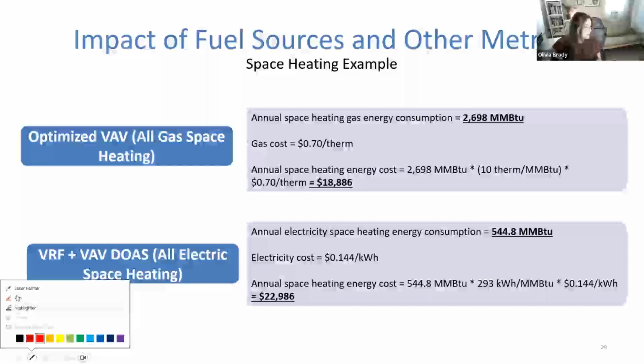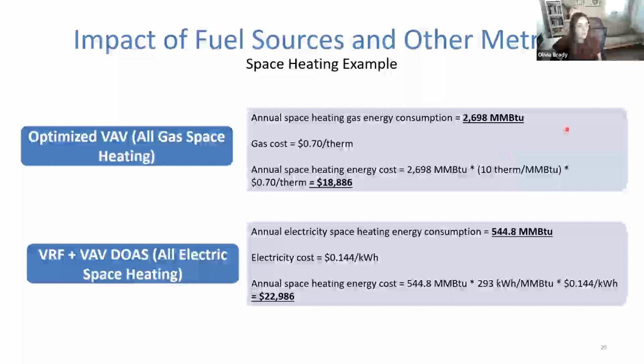So in the first option, the optimized VAV, the annual space heating gas energy consumption is approximately 2,700 MMBTU. Well, let's compare that to the annual electricity space heating energy consumption for the all electric. It's only 544.8 MMBTU. So you would look at this and you would say, great, the VRF has so much less energy consumption.